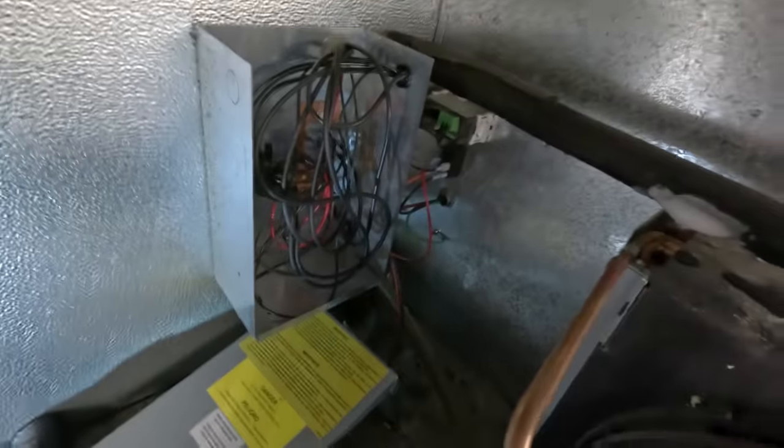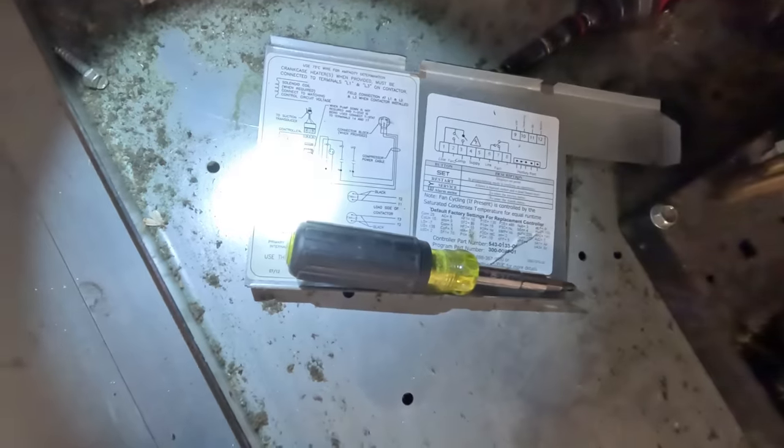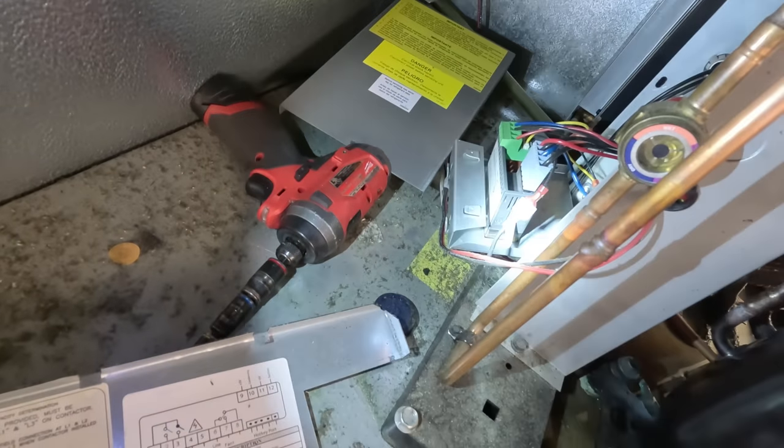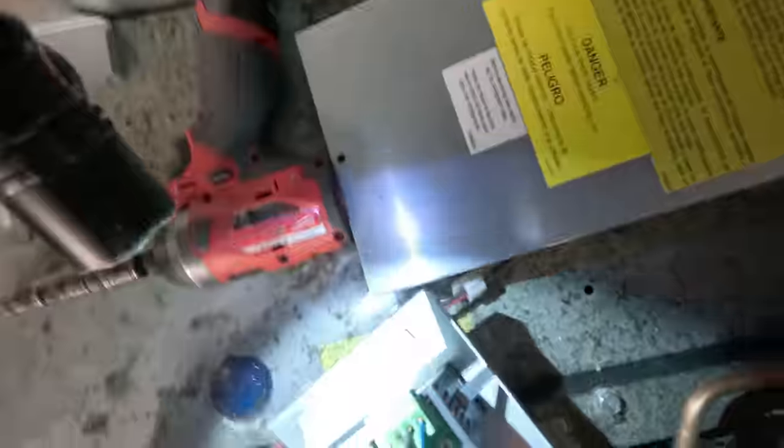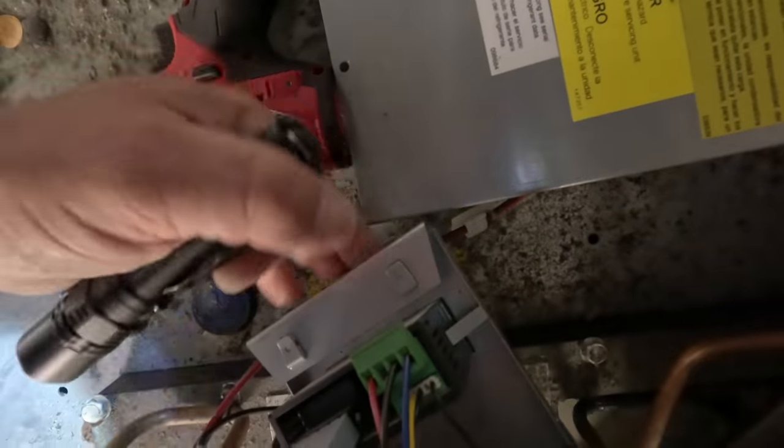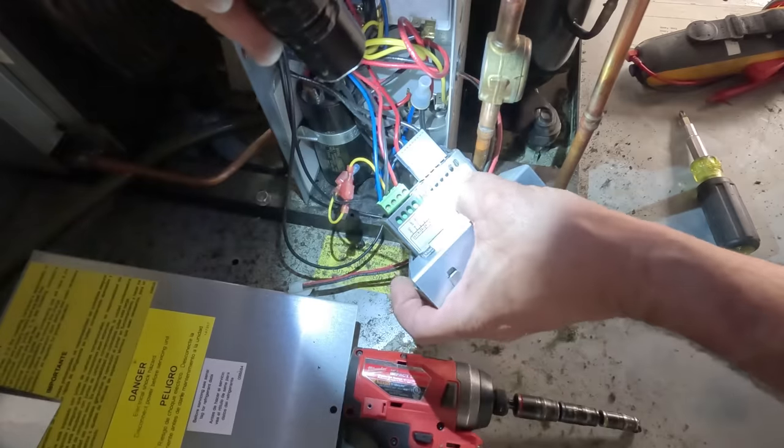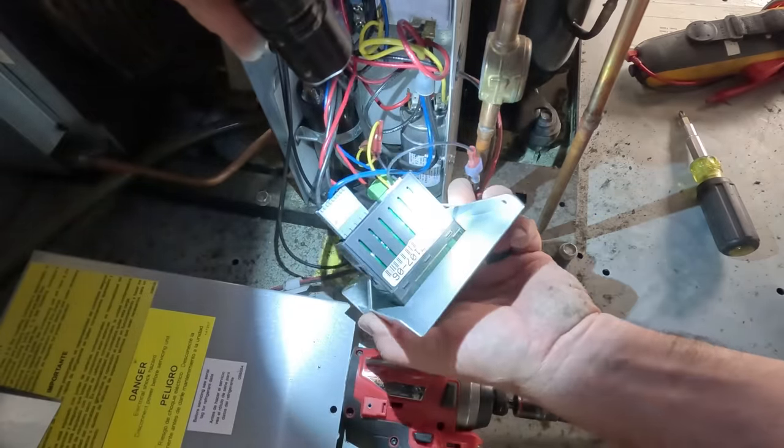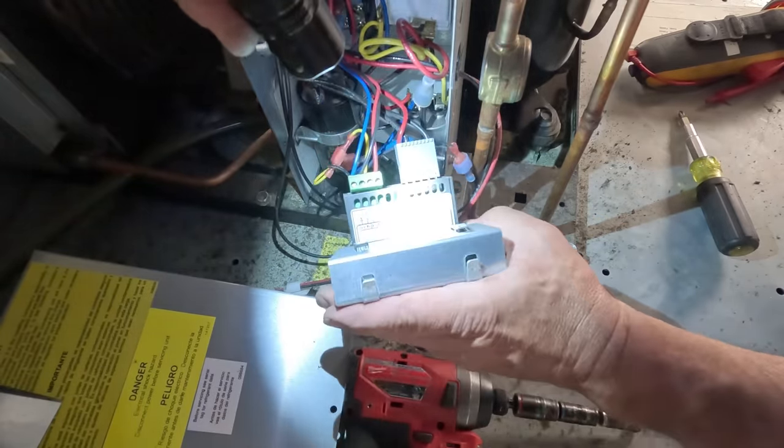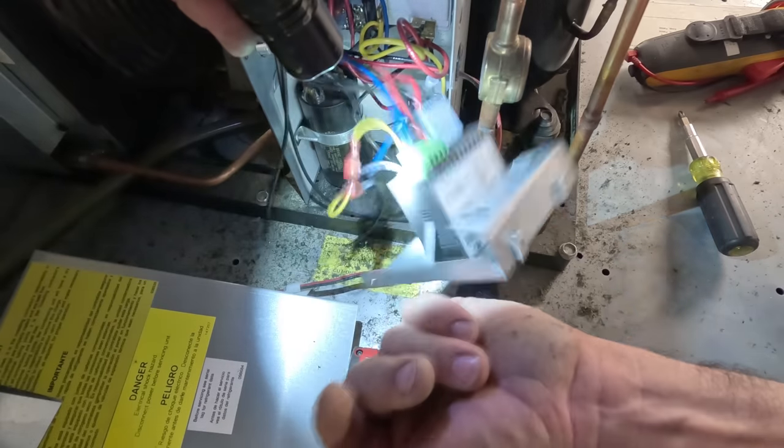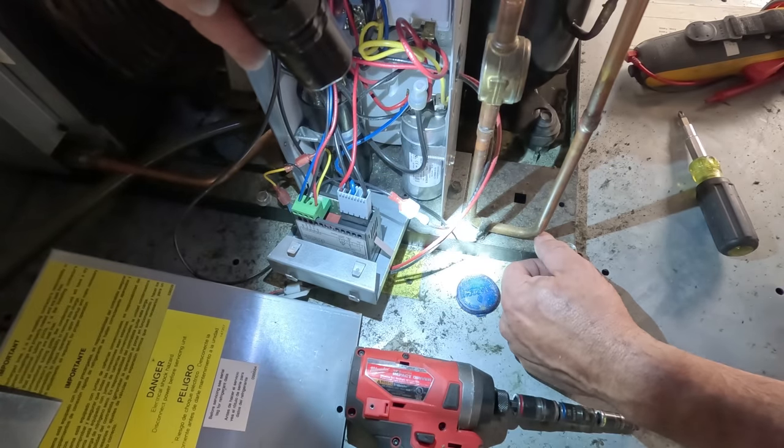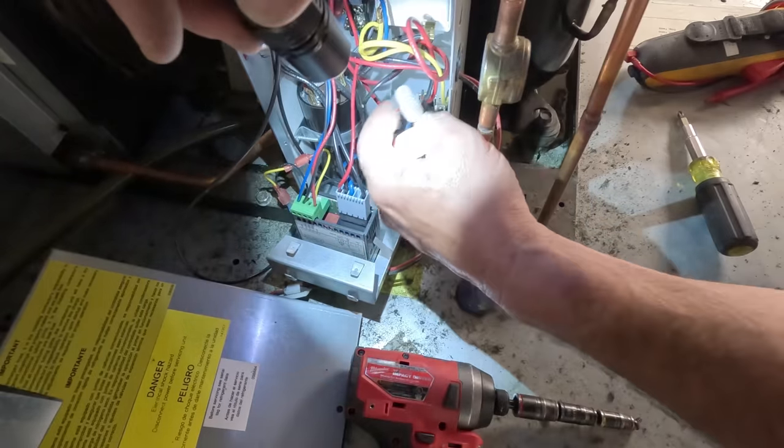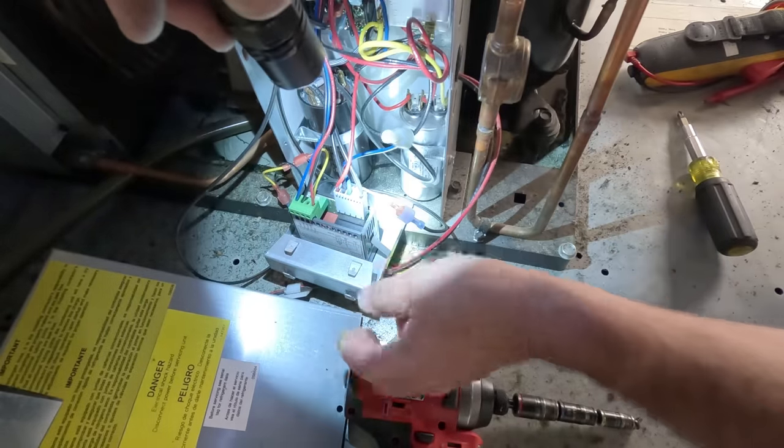Oh, I haven't killed the breaker to this thing. Red, black, and blue, which I only have black and red there. Looks to me though, this little controller here must control the compressor. That would make sense. Yep, right there's the compressor. So the relay's built into this thing. So they got this fancy device there to shut the compressor down. So you end up buying a whole new controller. We're not going to have this.